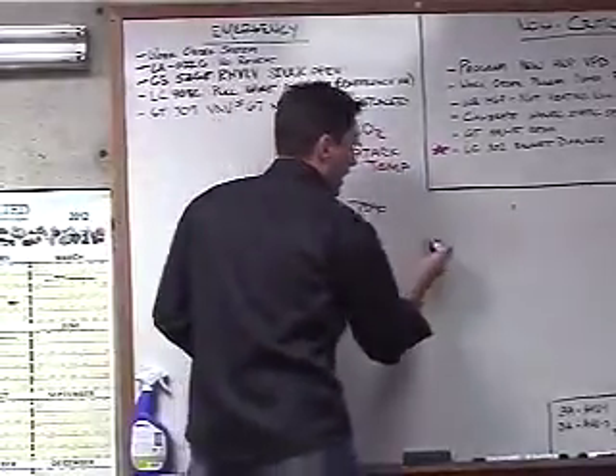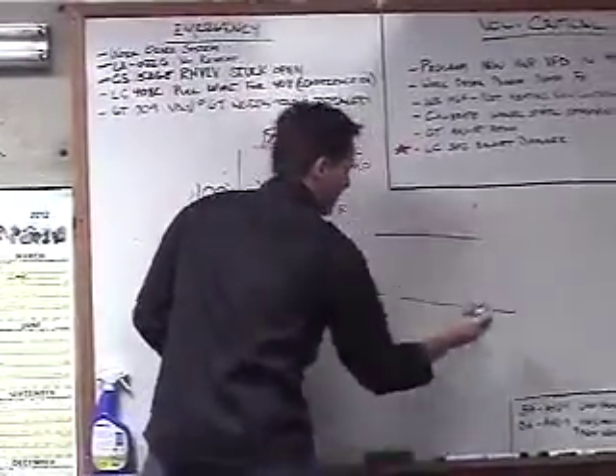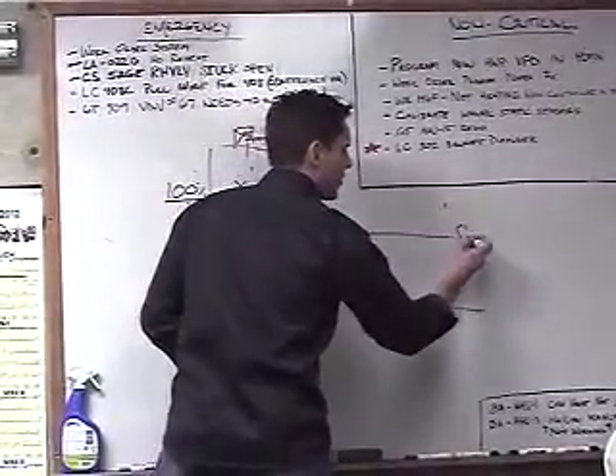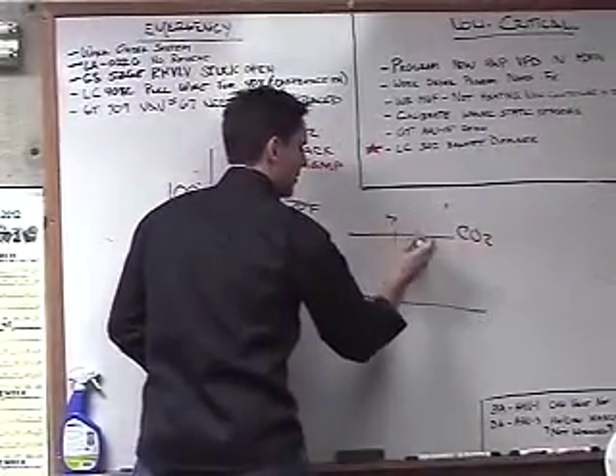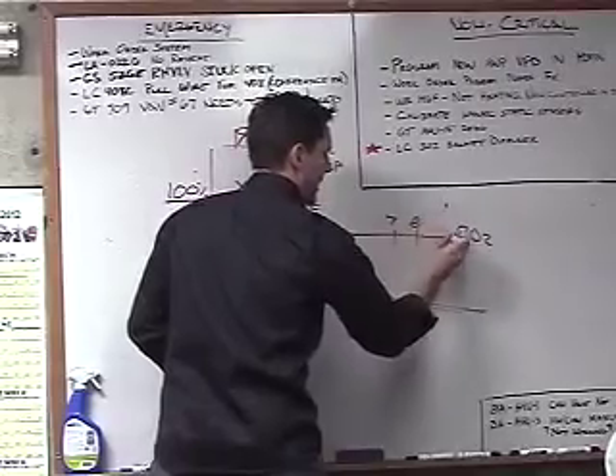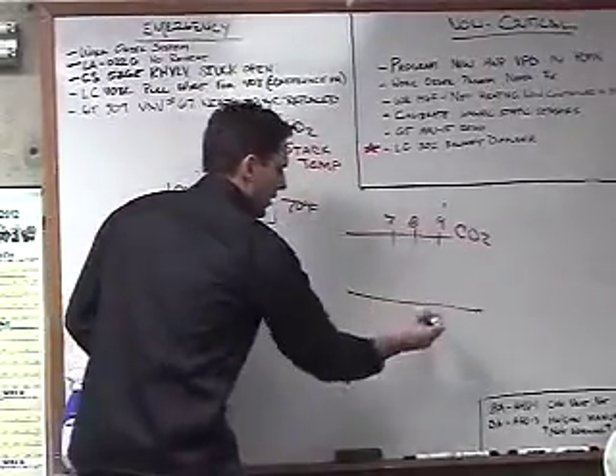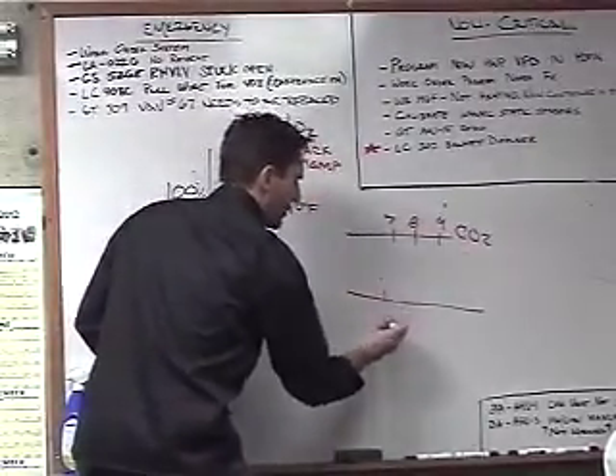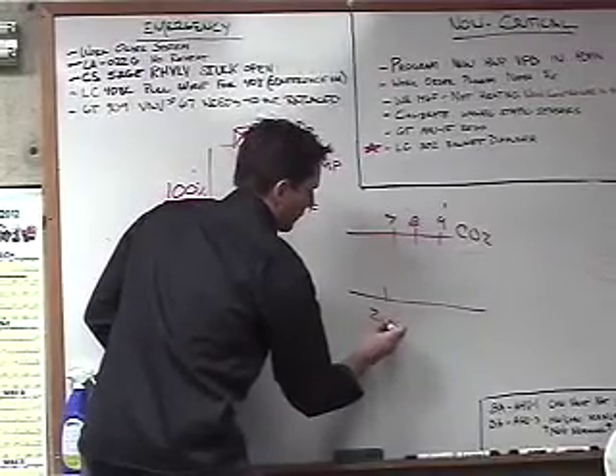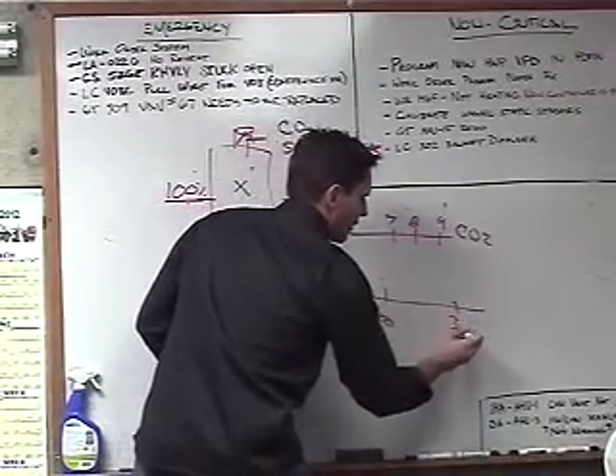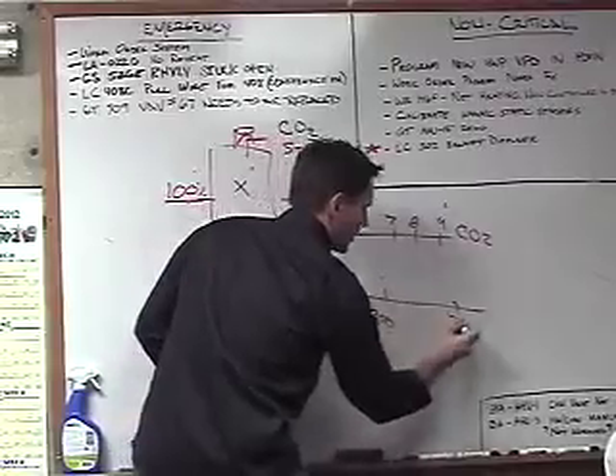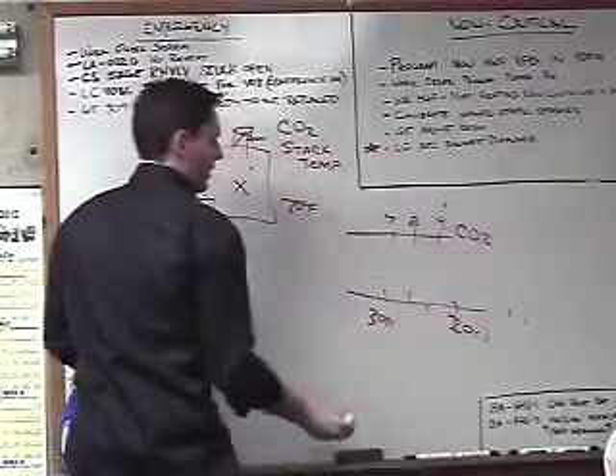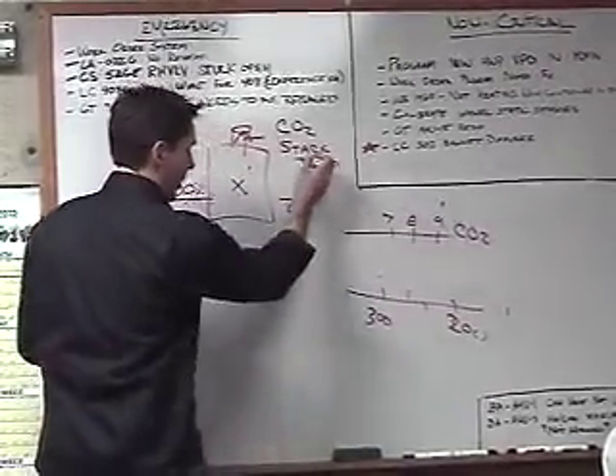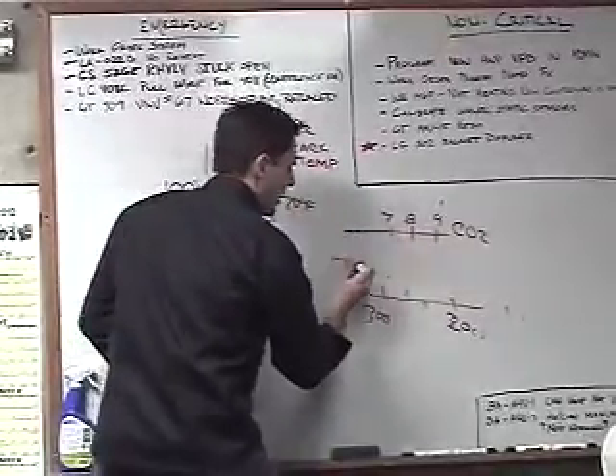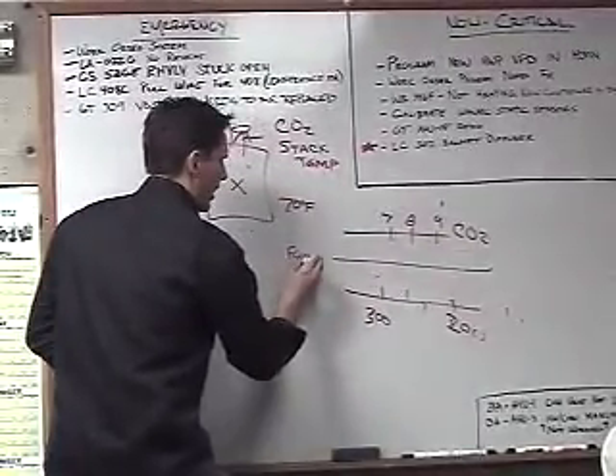So if we were to take a nomograph for something like this, this would be my CO2 line, and it would be 7%, 8%, 9%. Down across the bottom would be my temperature. So we'd be, maybe 200 degrees, I'm sorry, wrong one, 300 degrees, 200 degrees, and so on. This is my net stack temperature and my CO2. And then this line would be my flue loss.